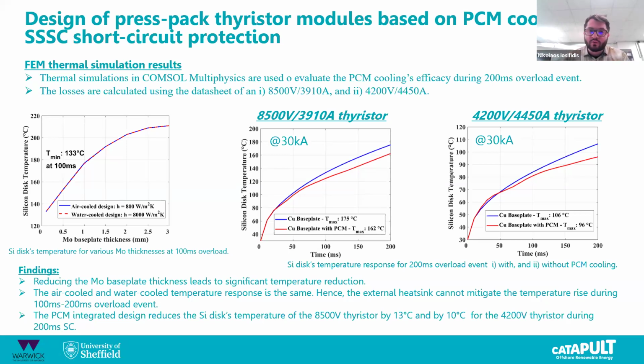And now if you see the graphs on the right, in the middle and on the right, we can see a 13 degrees C reduction using this PCM at 30 kA current, and a 10 degree reduction in the 4.2 kV thyristor. For the middle one, it actually takes it from the maximum rating to slightly less than that, which in silicon devices would probably avoid any instantaneous faults. Go to the next slide, please.